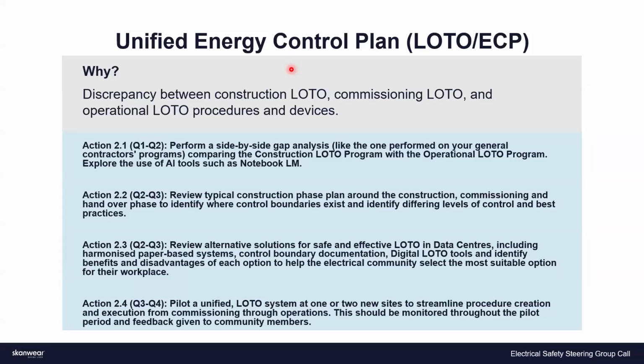So then you'd also be able to do that, and they also have the checklist. So the person doing the lockout tagout goes through the checklist. That's the proof that person had reviewed the procedure, and then has an electronic signature that says yes, I've reviewed this, and applied the locks properly. It also, in the US standard, requires that you have an annual review of your lockout tagout system, and that's an easy way to do it as well.